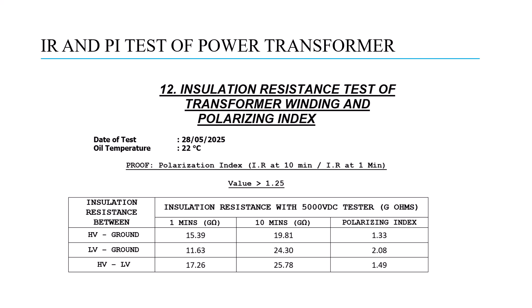The last slide shows actual practical results of the IR test. The test date and temperature are recorded, and the recommended PI value is greater than 1.25. On the left side we have three configurations: HV to ground, LV to ground, and HV to LV. Results at 1 minute and 10 minutes are shown in gigaohms. The polarization index values are 1.33, 2.08, and 1.49 respectively — all good and within recommended values. Thank you for watching.